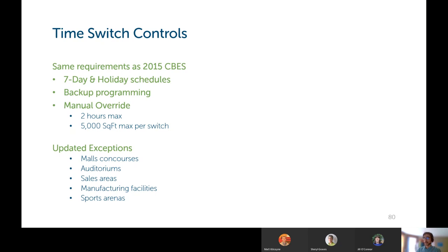Time switch controls, these are the same requirements as in the 2015 code. You need to have 7-day and holiday schedules, backup programmable in case the power goes out, manual override for up to 2 hours in a space that is no larger than 5,000 square feet per override switch. There's a couple of exceptions that have been added to where time switch controls are needed. Listed here: mall concourses, auditoriums, sale areas, manufacturing areas, and sports arenas. There are others in there as well, but those are the updated ones.